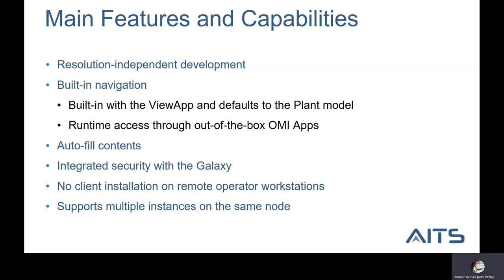Another feature is that InTouch OMI is a multi-threaded application, unlike InTouch for System Platform, which is a single-threaded application. There is another thing coming with InTouch 2020. Just before that, InTouch OMI 2017 doesn't support the .NET client controls, like the Alarm client control and Trend client control.